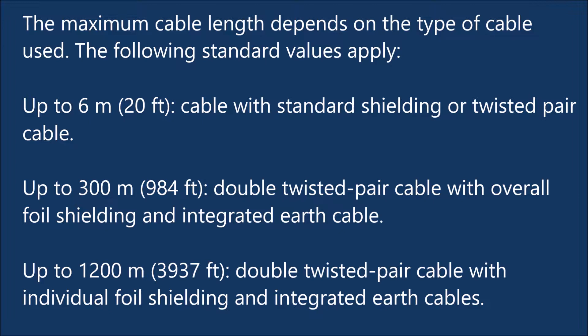Up to 300 meters (984 feet) — double twisted pair cable with overall foil shielding and integrated earth cable. Up to 1,200 meters (3,937 feet) — double twisted pair cable with individual foil shielding and integrated earth cables.